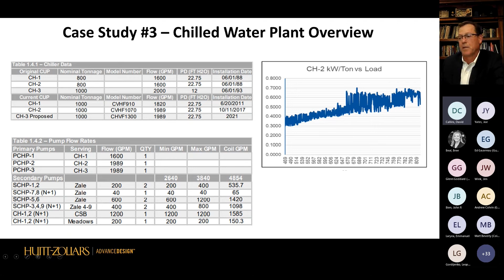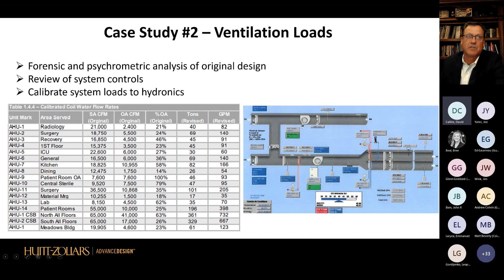And we did the forensics of the air handling equipment. And we saw in the 80s, they didn't have good spreadsheets or whatever, but the tonnages were way off. So we saw the original design, and this is what you really need if you're going to do these conditions. And some of the air handling units bypass coils. Up north, we would put face and bypass dampers so the air could go one path or the other. This was bypassing the cooling coil, so it's really hard to maintain humidity control. You can see they're trying to maintain 40 relative humidity in the ORs, and they're not. This is one of the reasons as well. So I think originally, just from the forensics, it was doomed from the start, and that just got worse.